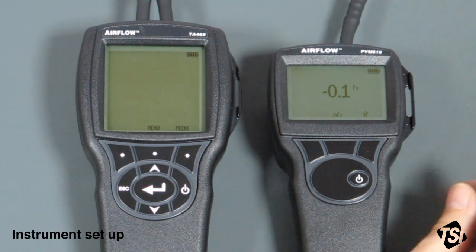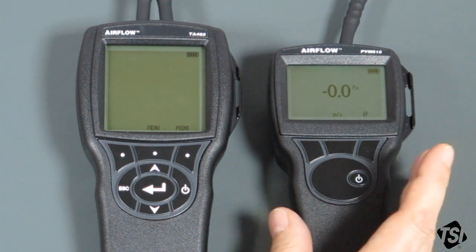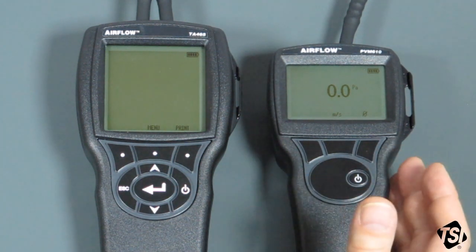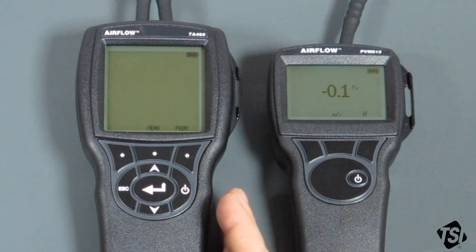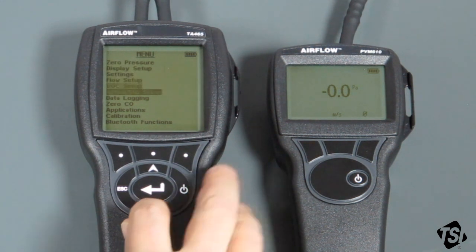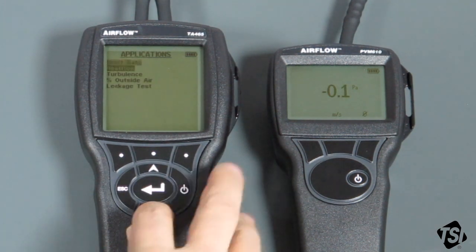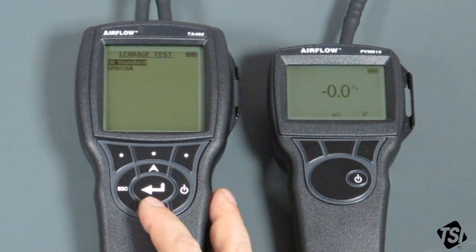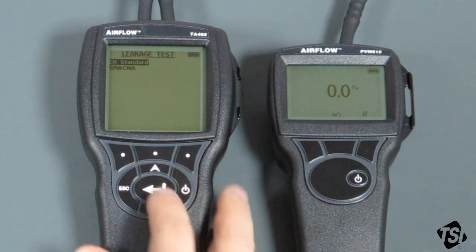We now have everything connected up and ready for the test — we just need to set the instruments up. The PVM610 has already been zeroed. Make sure you have the right unit selected: Pascals or inches water gauge. In this case we're going to use Pascals. For the TA465P, we now have to set up the leakage application. Go into the menu, go down to Application using the arrow keys, press the centre Return key, and we're in the Applications menu. The bottom application is the one we want: the Leakage Test application. Select Return. There are two options — the EN Standard and the SMACNA, which is the American one. In this case we want to carry out the European test, so we select that one.